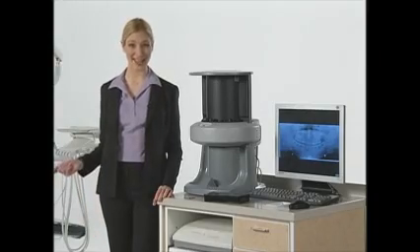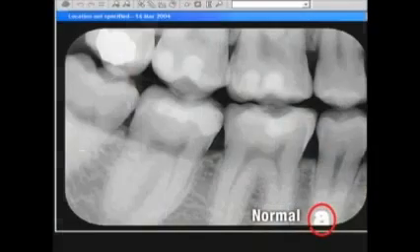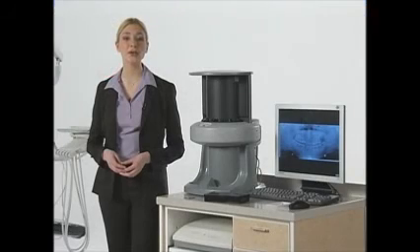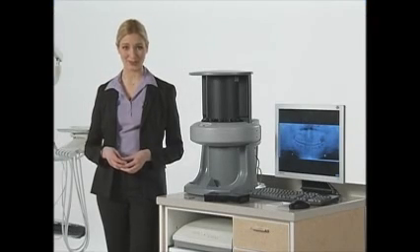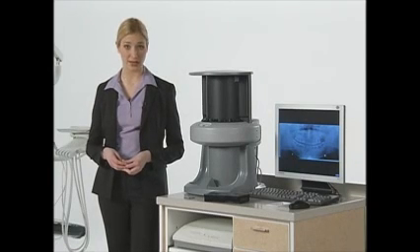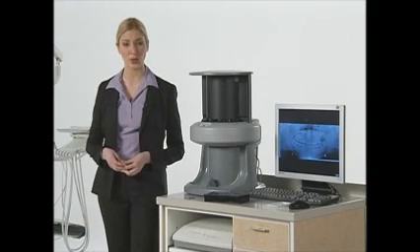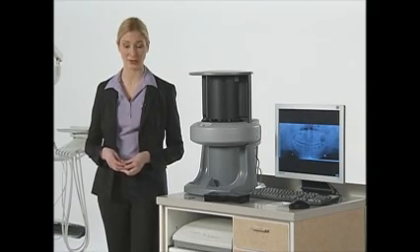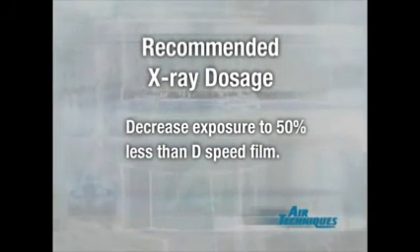Then, after scanning, the image on the monitor will appear normal or mirrored. That, coupled with your knowledge of dentistry, will enable you to properly orient the image. When you're ready to expose the image, you may have to decrease the x-ray dosage, depending on which equipment you own and the film type you have been using. A good starting point is an exposure that is 50% less than D-Speed film. You may need to experiment a little bit to determine the best setting.